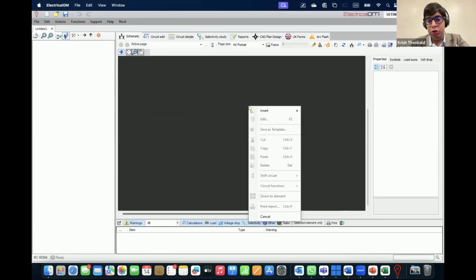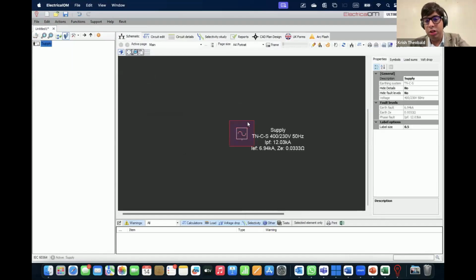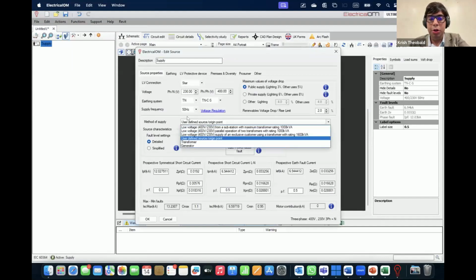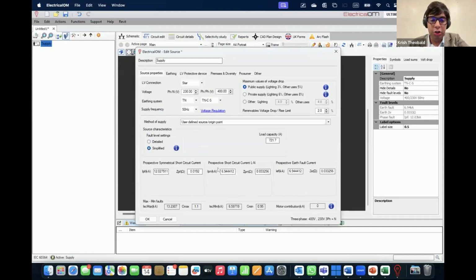Anyways, so let's just go through a very, very simple situation. So if I were to consider a simple source, I'm just going to add a source for now, and then we will look at the actual model that we will develop. So say it is a simple user-defined source. We've got certain earth fault loop, prospective short circuit currents, prospective earth fault currents, and obviously symmetric short circuit currents. We've set our voltage supply. It's a TN-C-S installation, let's say.